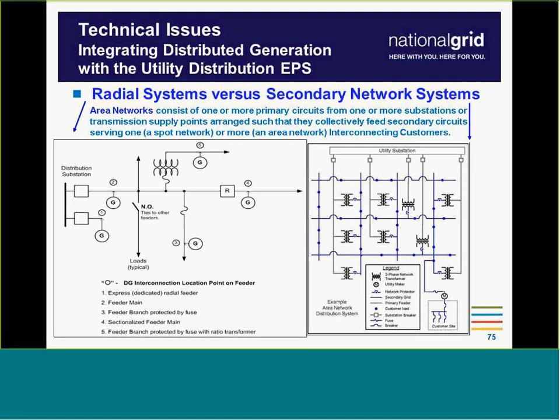Another issue, a common thread throughout this presentation, is DG saturation. We have a lot of substations where we've exceeded screens for risk of islanding, the 67% of minimum load screen, and exceeded screens for 3V0, which is transmission ground fault protection, meaning you're capable of backfeeding into transmission and also capable of overloading your distribution circuit.